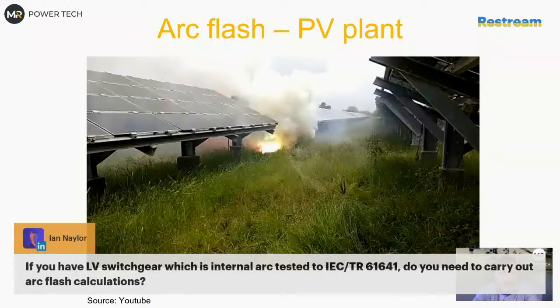If your time is not too long, because it might be that your switchgear is tested for 300 milliseconds, which is typical for cable connections. And I can tell you that 300 milliseconds on the incoming cable connections is very low time, because it will be protected by medium voltage protection, and it's typically always higher than this. And so you might see that, okay, maybe you have a 1 second rating. There are different solutions. But yeah, you need to carry out Arc Flash calculation.